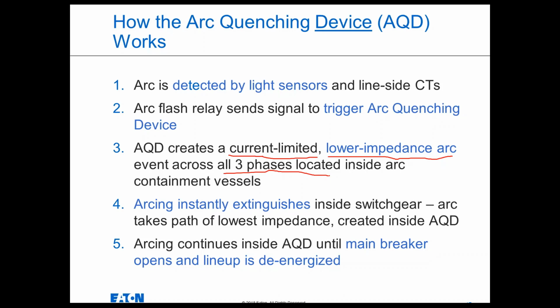So the arc quenching device works on the same concept as a crowbar device or bolted fault device, in that it creates a path of lower impedance for that energy to follow whenever an arc flash is detected. The difference is that it actually introduces some impedance to reduce that peak fault current. So it's not only protecting the switchgear itself, but also protecting the upstream equipment from dangerous electromechanical forces that can occur when you draw peak fault current.